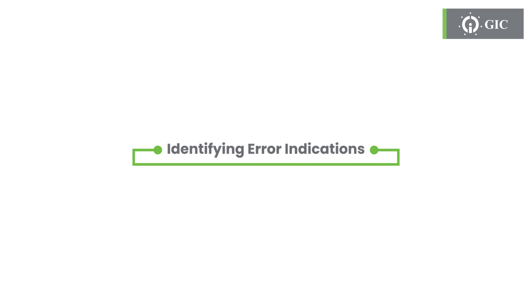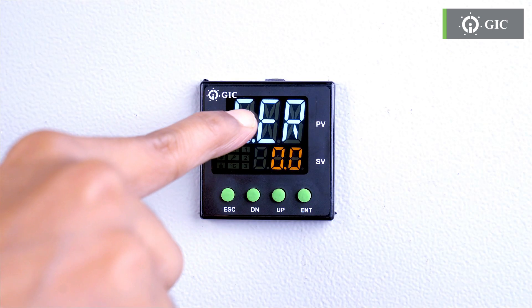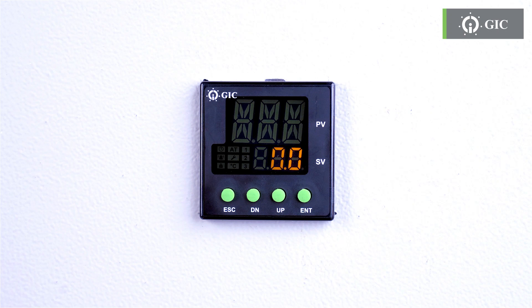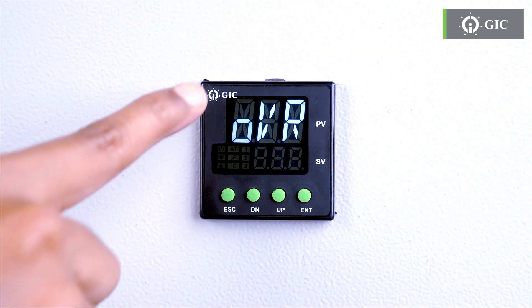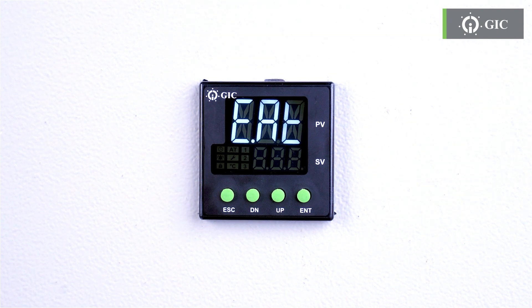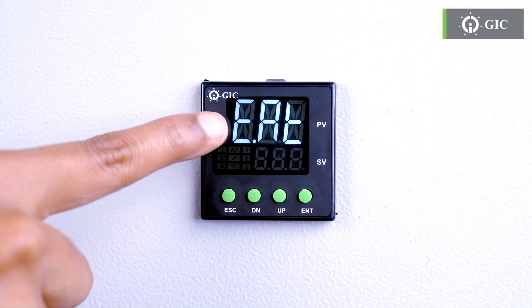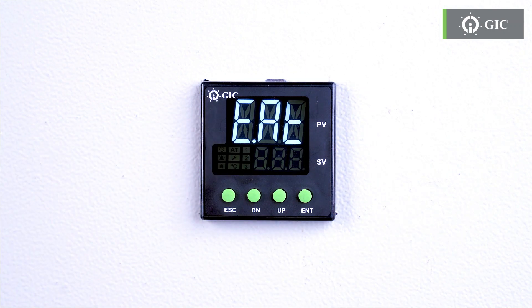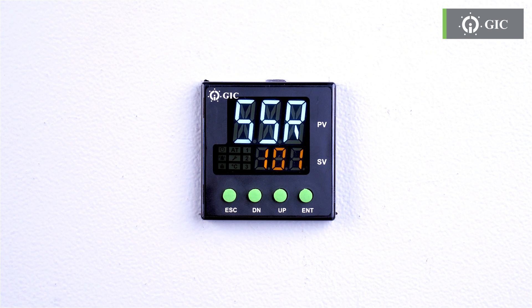The updated temperature controller is smart to point out errors when something goes wrong, so keep an eye for the following indications. If it says S.ER, there might be an issue with the sensor — open or break error. If you see OVR, it's indicating an overrange error. And if it's UNR, it's telling you about an underrange error. If you see E.AT, it means an error in autotuning. If it says SSR, it means there's a short circuit detection. Now you can even detect errors in your system.